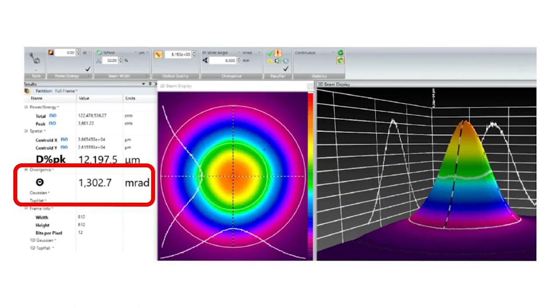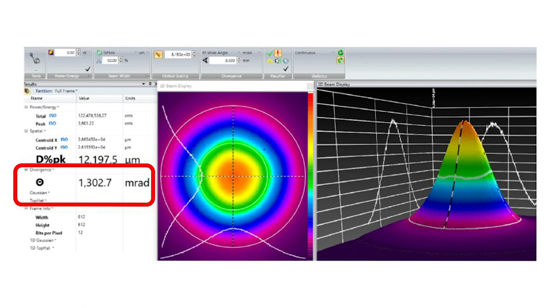When we enter the source-to-diffuser distance into the BeamGauge software, BeamGauge then calculates and displays the beam's divergence angle. If we used a regular sensor, this would only be possible for very small divergence angles, because of the angle dependence. The WBI, with its 45mm clear aperture and special diffusive screen, lets us work with beams whose divergence angle is up to plus or minus 70 degrees.